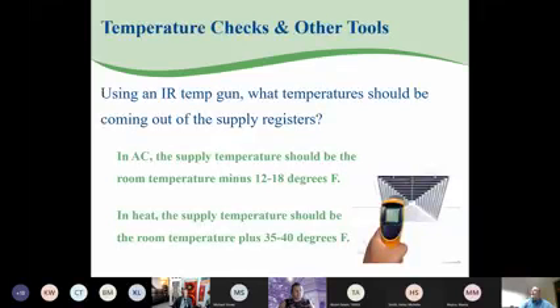Some simple temperature checks can be made at supply registers with an IR temp gun. What should the temp be? In AC mode, the supply temperature should be the room temperature minus 12 to 18 degrees. In heat mode, the supply temperature should be the room temperature plus 35 to 40 degrees.